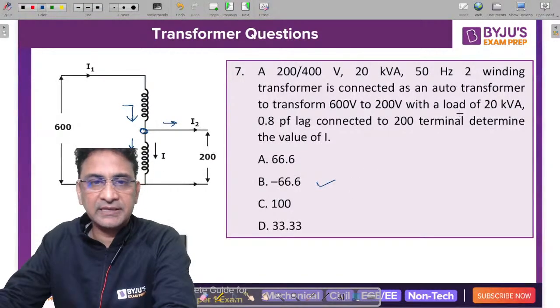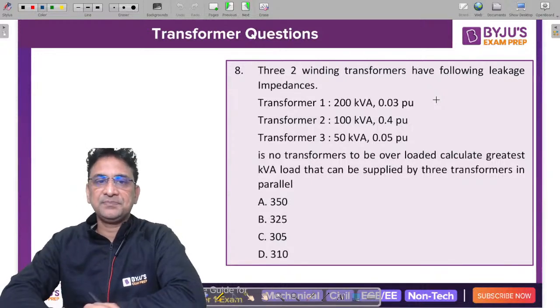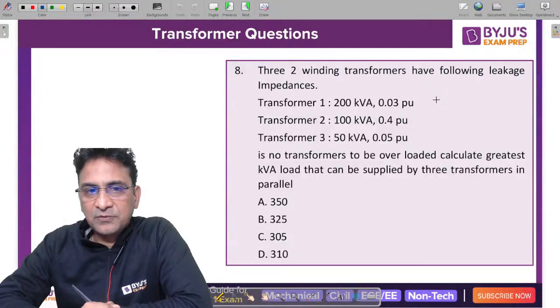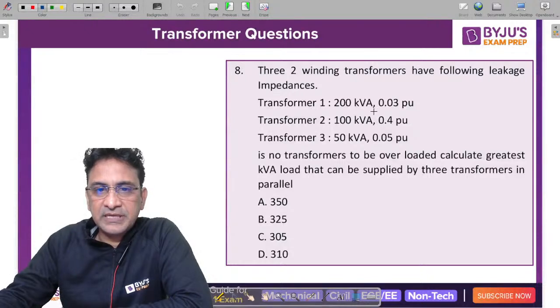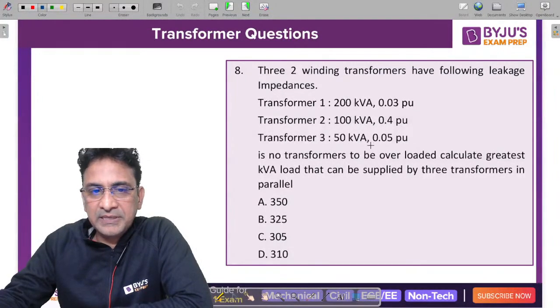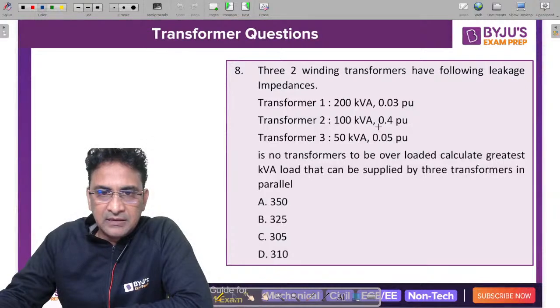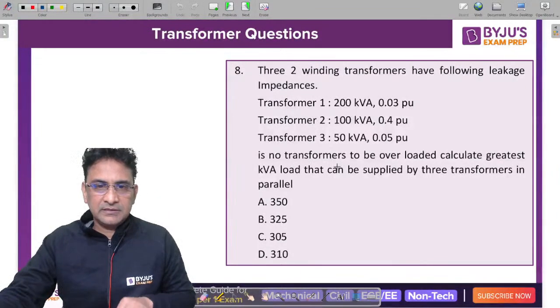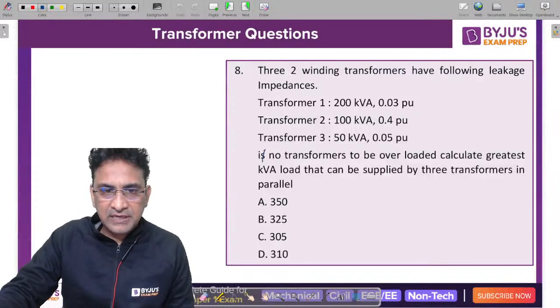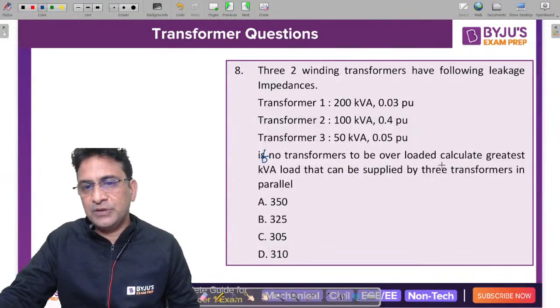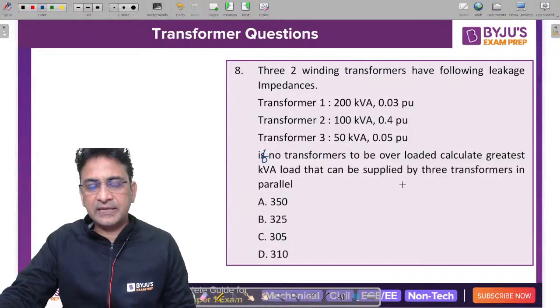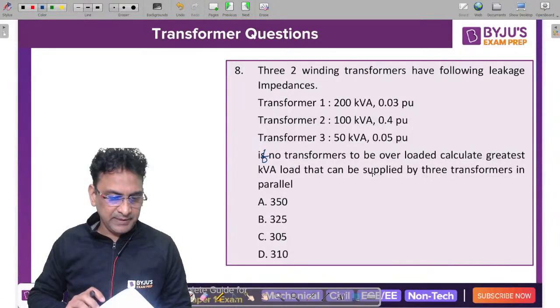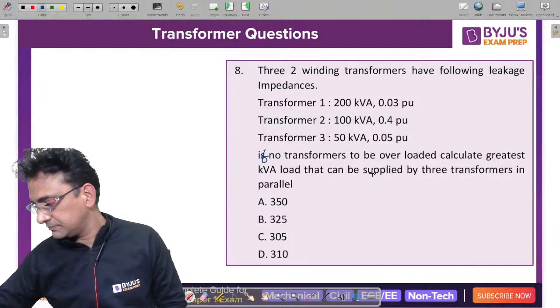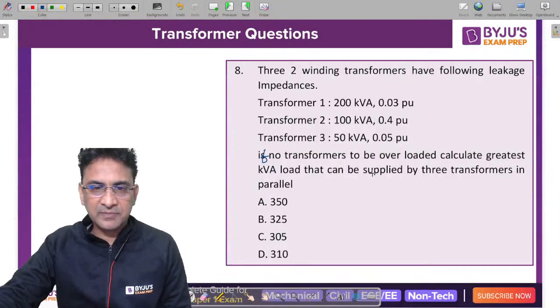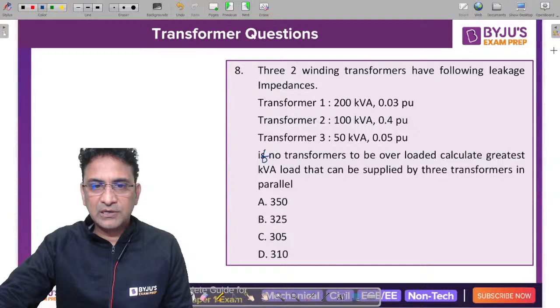Mostly all students answered this question correctly. Let's now move to the next question. Three two winding transformers have the following leakage impedances. The three transformers are rated 200 kVA, 100 kVA and 50 kVA. If no transformer is to be overloaded, calculate the greatest kVA load that can be supplied by the three transformers in parallel without overloading a single transformer. How much load can be supplied by the overall parallel transformer?